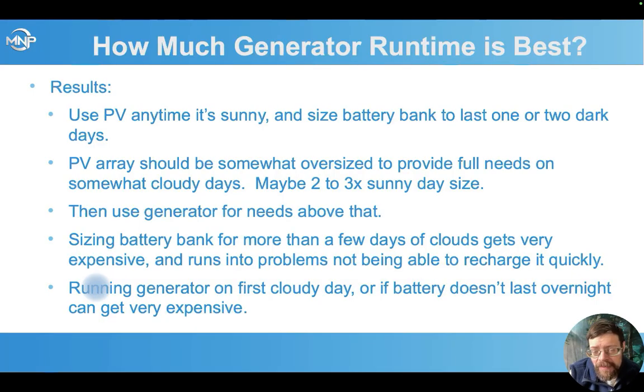So that's kind of an average. It can vary on your particular situation, but generally, if you're trying to go for days and days of really bad, cloudy, dark weather, that's where it makes sense to just switch to a generator for backup. And typically you'll find it's 10% of the total power, maybe somewhere around there. But don't be starting your generator on the first cloudy day or just because you can't make it to the next morning.